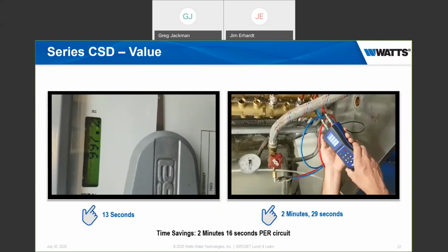Okay, next question. Since the flow rate is set according to what's required, is there a pressure drop range for each valve, or is it constant? Yes, there is a pressure drop range. There is a CV value assigned to the valve. So with each valve, on our ES sheet, you will see there's a range of flow rates that is recommended for it. One of the things that you'll notice on the ES sheet is that the low end of the flow rate is really low.